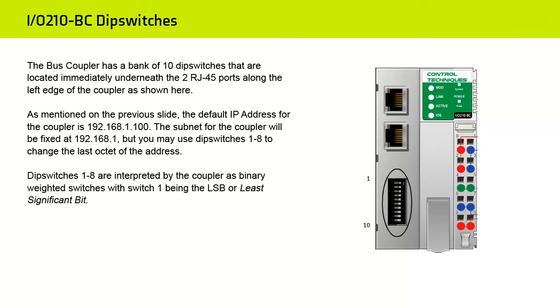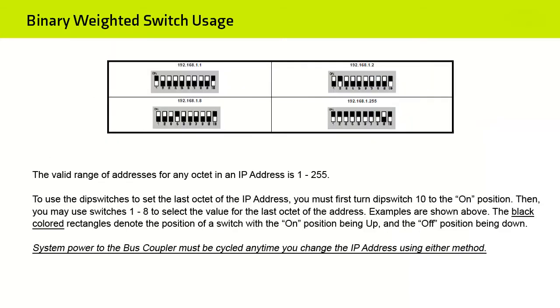As mentioned on the previous slide, the default IP address for the Coupler is 192.168.1.100. The Subnet for the Coupler will be fixed at 192.168.1, but you may use DIP switches 1 through 8 to change the last octet of the address. DIP switches 1 through 8 are interpreted by the Coupler as binary weighted switches, with switch 1 being the least significant bit. The valid range of addresses for any octet in an IP address is from 1 to 255.